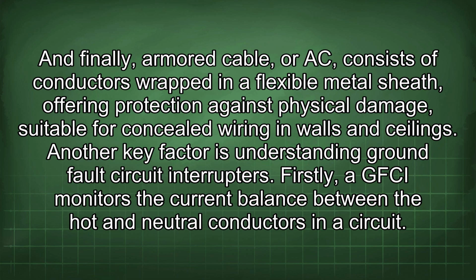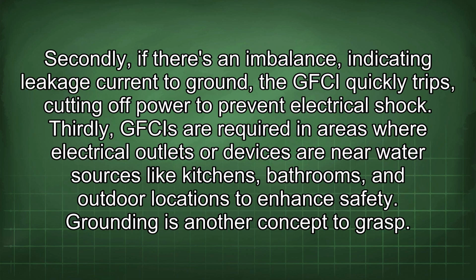Another key factor is understanding ground fault circuit interrupters. Firstly, a GFCI monitors the current balance between the hot and neutral conductors in a circuit. Secondly, if there's an imbalance indicating leakage current to ground, the GFCI quickly trips, cutting off power to prevent electrical shock. Thirdly, GFCIs are required in areas where electrical outlets or devices are near water sources like kitchens, bathrooms, and outdoor locations to enhance safety.